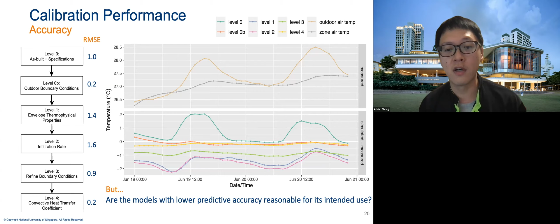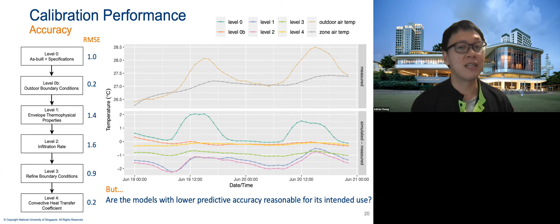And then further investigation revealed that this was because the boundary conditions of the floor and ceiling plenum were actually different. So again, based on measurements, we input that into the model. And then lastly, including the CHTC, your convective heat transfer coefficient, we managed to reduce the root mean square error back to 0.2 degrees Celsius.